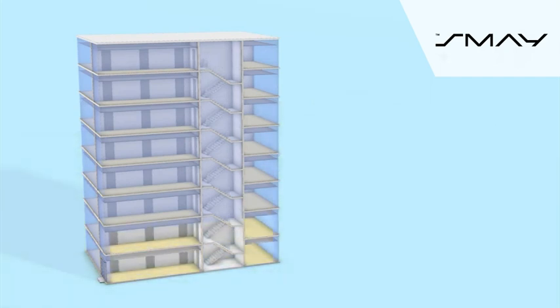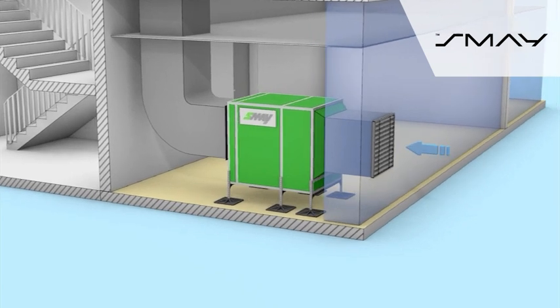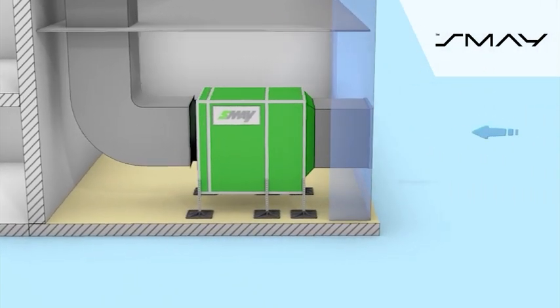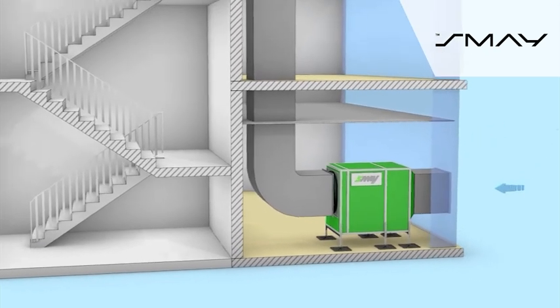In case of low-rise and medium-rise buildings, in order to protect vertical escape routes against smoke infiltration in case of fire, it is sufficient to use a single SMAY FC unit. Such unit may supply air to any part of the protected staircase.